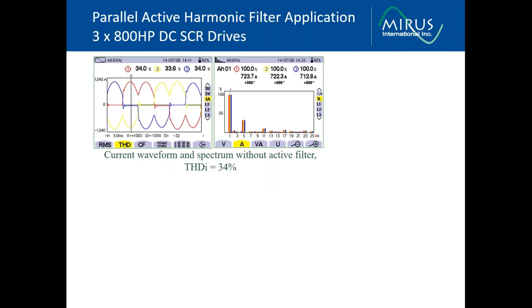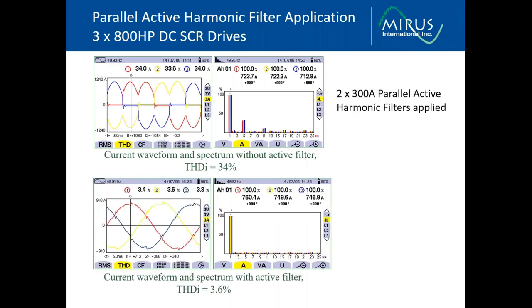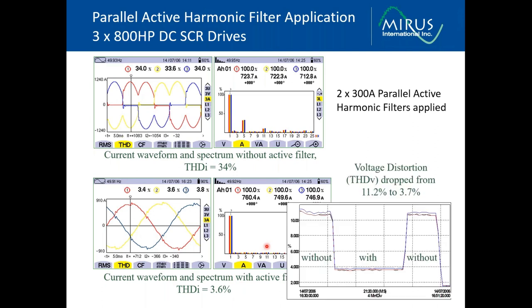In this example, there were two 300 amp parallel active filters that were applied to three 800 horsepower DC drives. So we show the current of the DC drives before the application of the active filter. We can see that the current distortion was 34%, predominant harmonic fifth. When we switched in the active filter, the upstream of the active filter was now drawing much lower current harmonics. And by drawing lower current harmonics, the voltage distortion on the bus was reduced as well. So we can see here, without the filter, we were at 11% voltage distortion. With the filter, we're down at 3.7%.